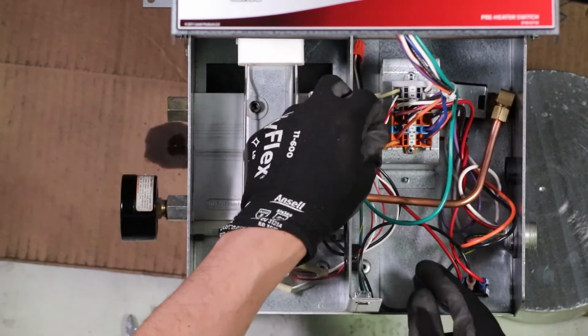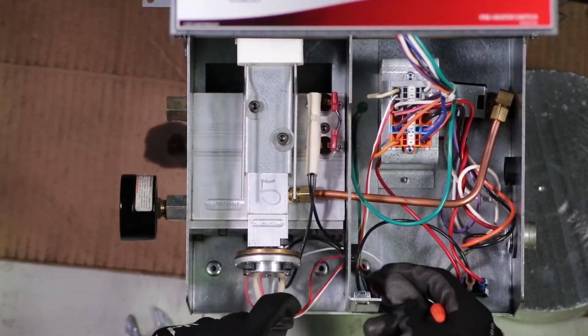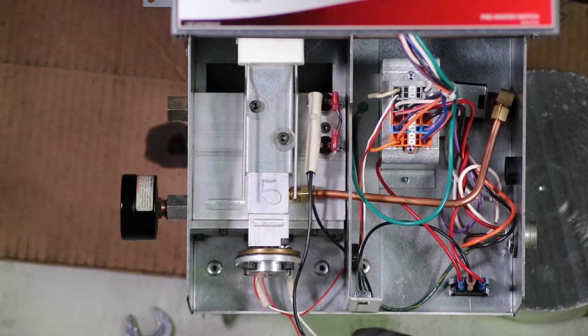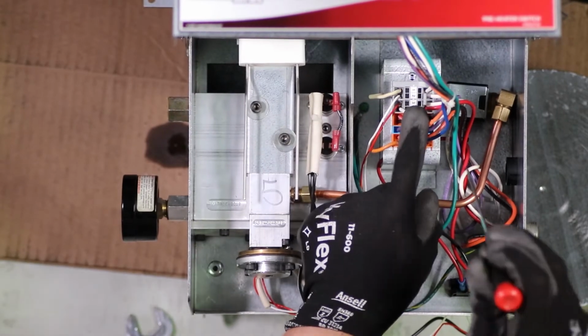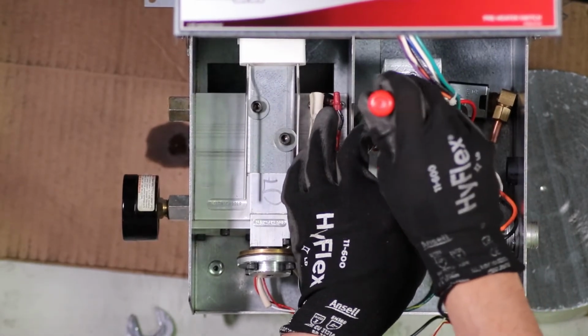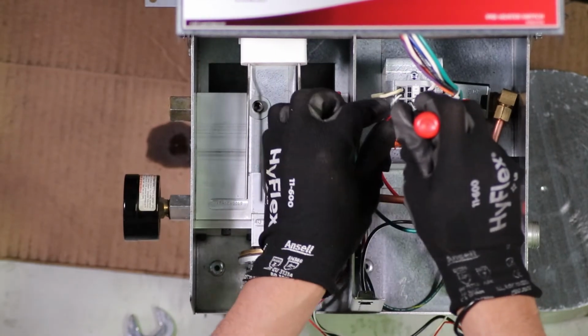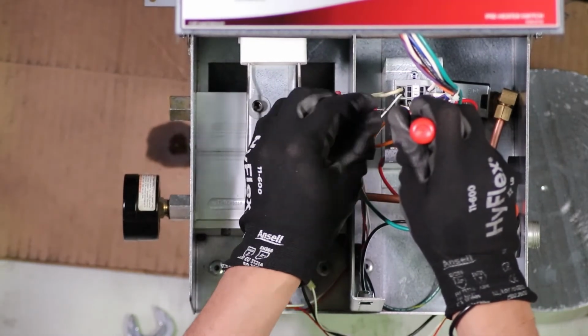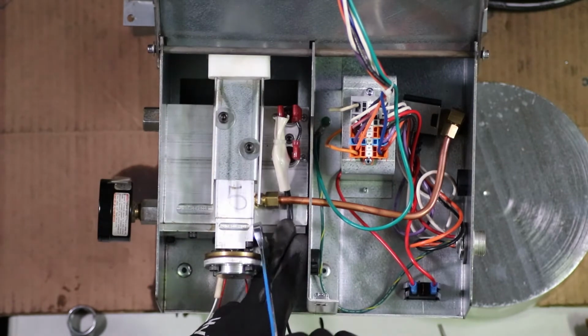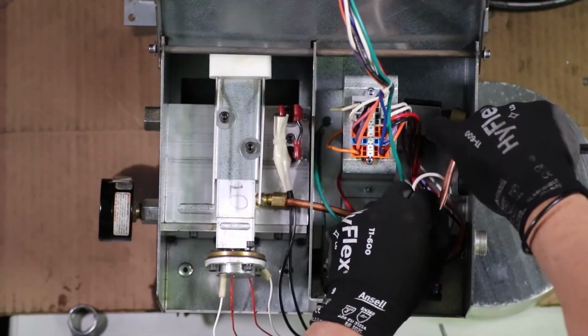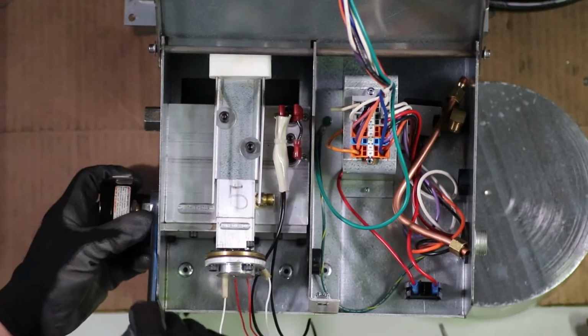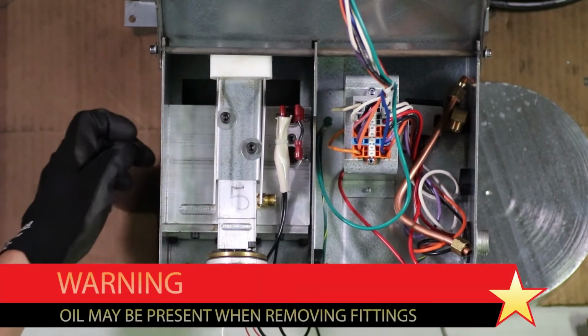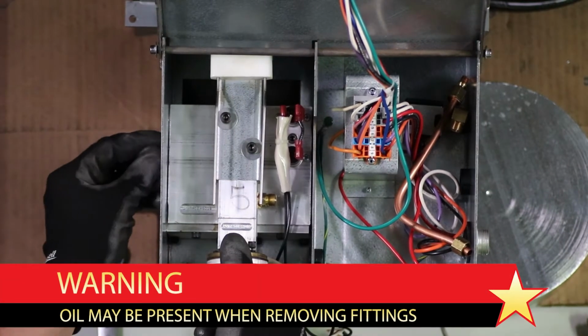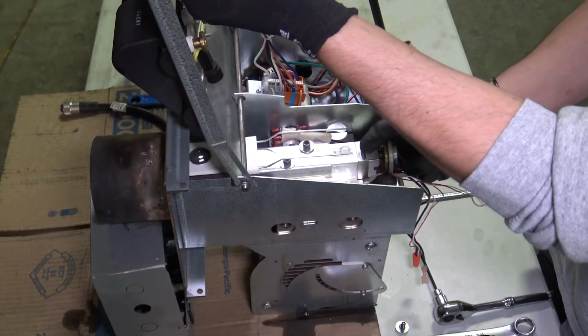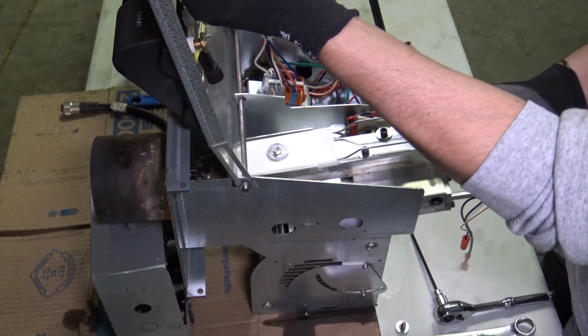Trace the wires from the preheater and make sure that the wire nut is on the same side of the burner as the preheater. Trace the remaining preheater wires to the burner's main terminal block and preheater switch. Make a note of where the wires connect, then disconnect them from the burner. Locate the copper air line, loosen the nuts on both ends, and remove it. Next, remove the gauge, fittings, and adjustment screw mounting the preheater to the burner chassis. You should now be able to lift and slide the preheater out of the burner.